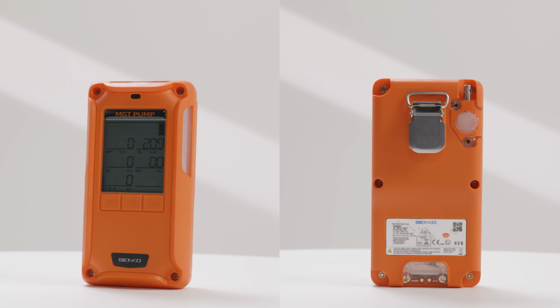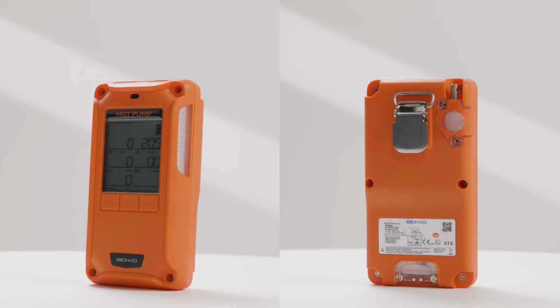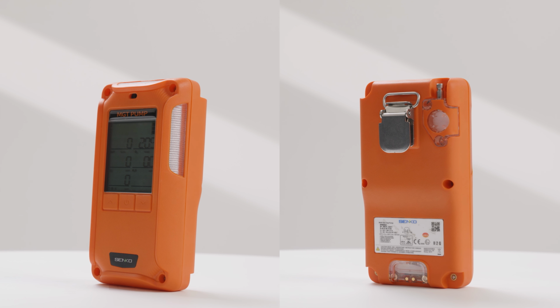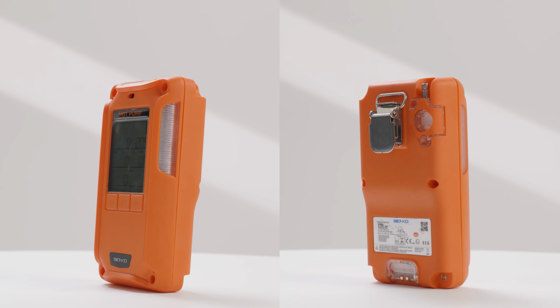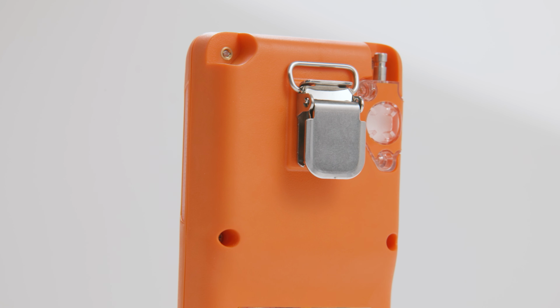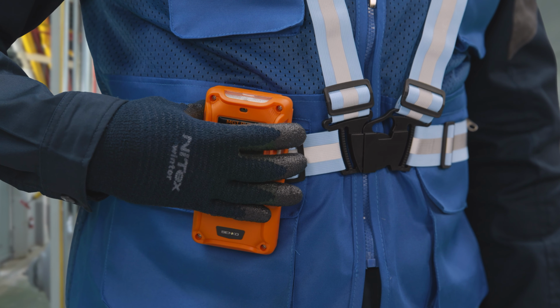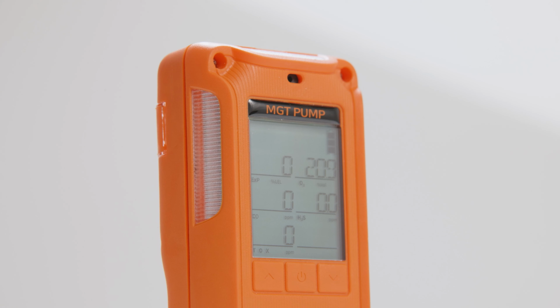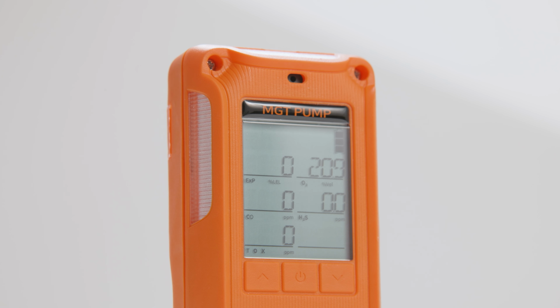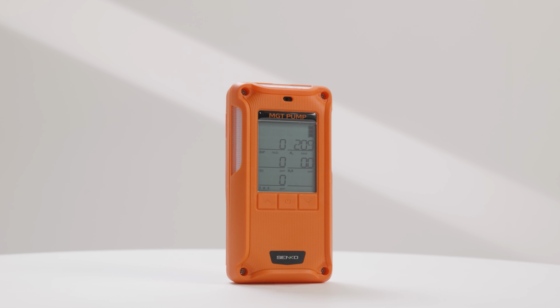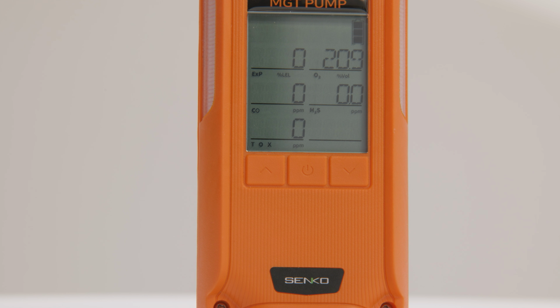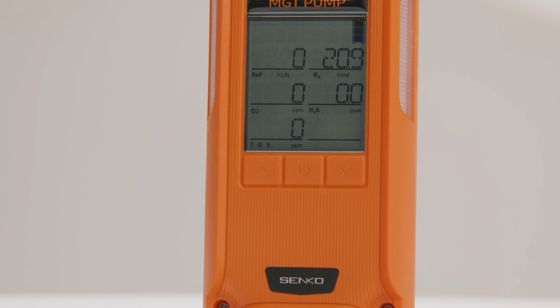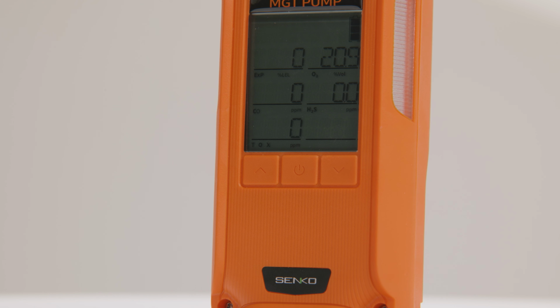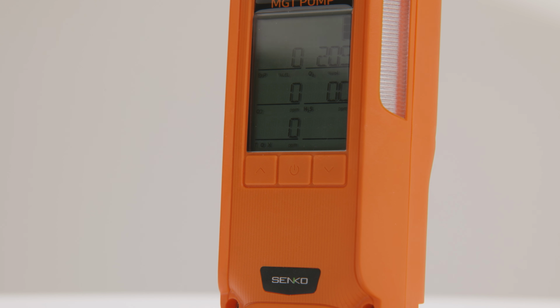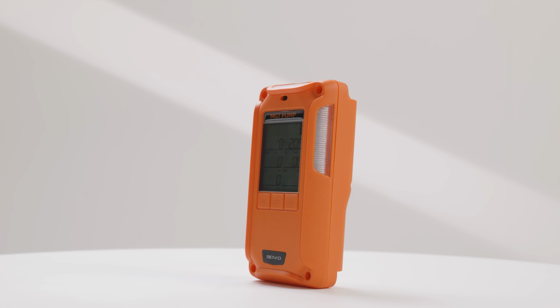Now, let's take a look at the appearance of the SP-MGTP. On the rear, you will find the gas inlet connected to the built-in pump. Through this inlet, the SP-MGTP actively draws in surrounding air, ensuring stable gas sampling even in environments with limited airflow. A belt clip and charging port are also positioned on the rear, allowing secure hands-free carrying and easy access for charging. On the front, the LCD display shows the real-time concentrations of up to 6 gases, along with key information such as alarm status and battery level, so users can quickly understand the surrounding environment. Below the display are 3 control buttons. The center button is used for power and selection, while the left and right buttons are used for menu navigation and setting adjustments, allowing simple and intuitive operation.